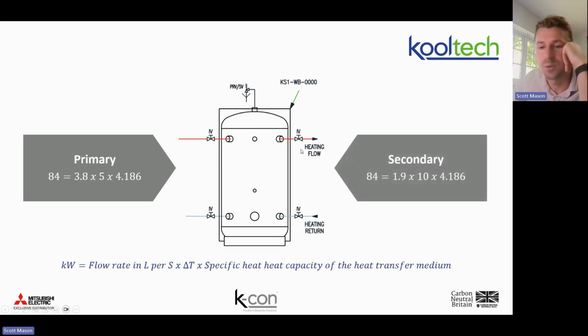And then because we've got this thermal break in place, which is the thermal store in its own right, it gives us flexibility on the secondary side. So if you want to have a wider delta T on the secondary side of that thermal store, you're absolutely welcome to. But the wider the delta T gets, the bigger this volume needs to be. And also that return tapping, probably a good idea. What we'll do, we'll manufacture the cylinder so that basically it's a little bit higher up, so it hangs around in the tank longer, rather than having it shoot straight across at a low temperature and go into the heat pump and return at a low temperature. But yeah, you can have a wider delta T on the secondary. That's absolutely fine, and that can obviously have a big impact when retrofitting, if trying to use some areas of existing infrastructure.